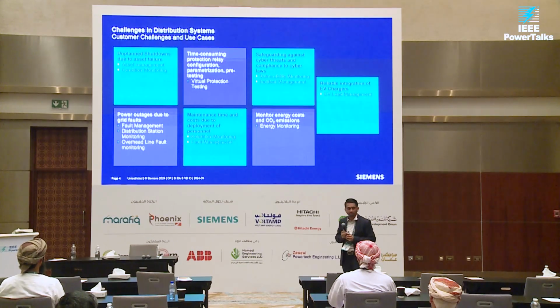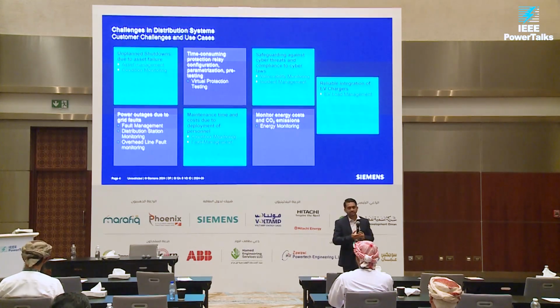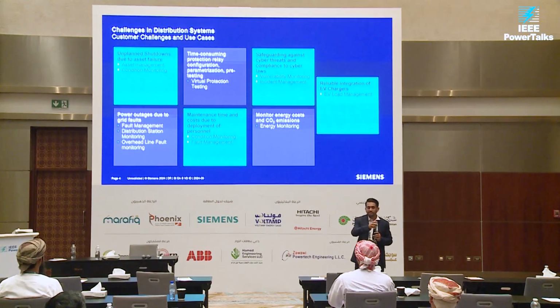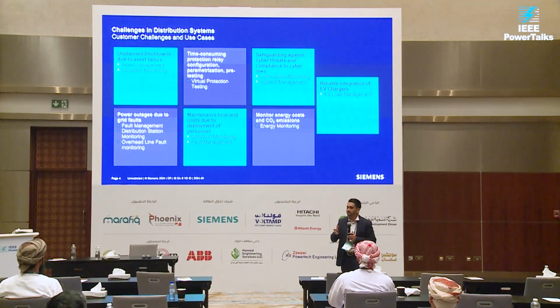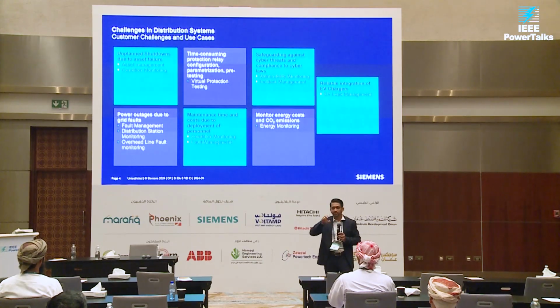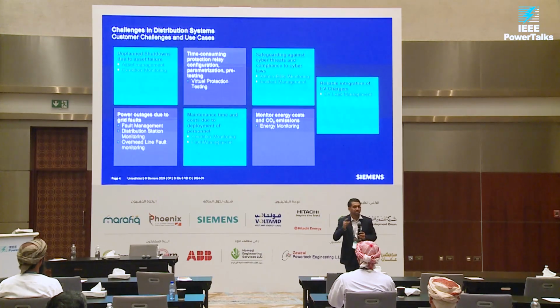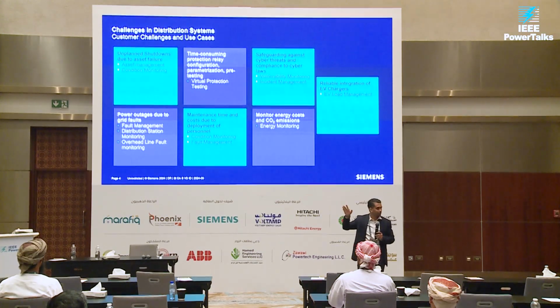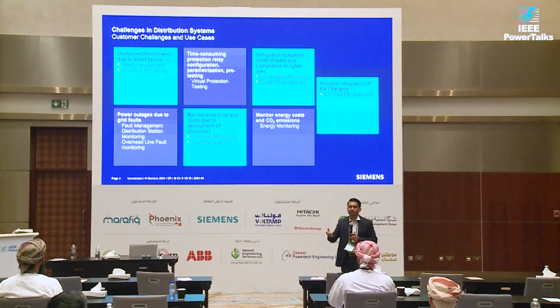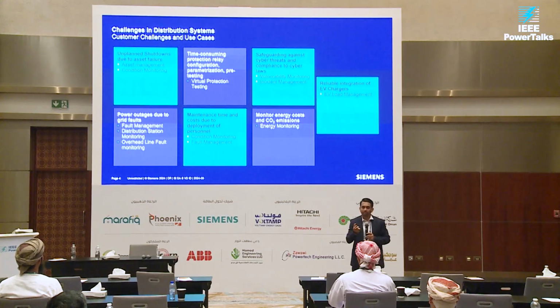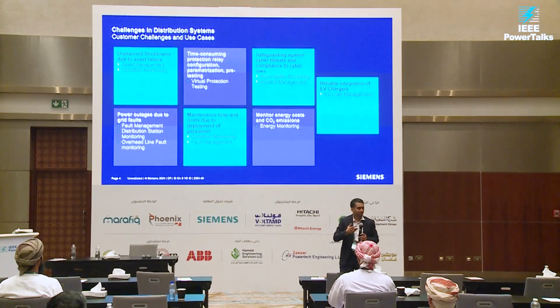Finally, cybersecurity. When we talk about interconnected systems - say an OETC station or NEDC substation - we connect relays to an RTU, and the RTU connects to SCADA. So we're interconnecting systems, and SCADA runs a lot of software, including commercially available operating systems like Microsoft's. That means they are vulnerable. Every software and electronic component has programs written into it by human beings, and we make mistakes.